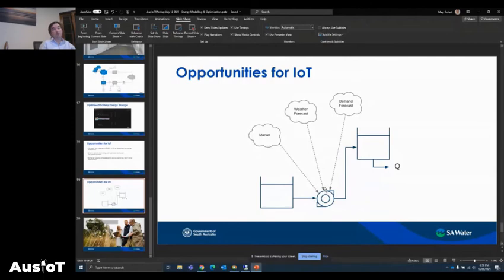What enables that kind of approach is that these devices aren't often connected to SCADA and just run locally with only awareness of what the tank levels are doing. By providing that extra IoT capability and awareness of what's happening in the energy market, it can still run in an autonomous way, but with a slightly more sophisticated control approach that can result in significant cost savings for the operation of those pumps. Even if they're not connected to SCADA and not actively controlled, they can be configured with a control algorithm that gives us a lot more benefit from an energy cost perspective.